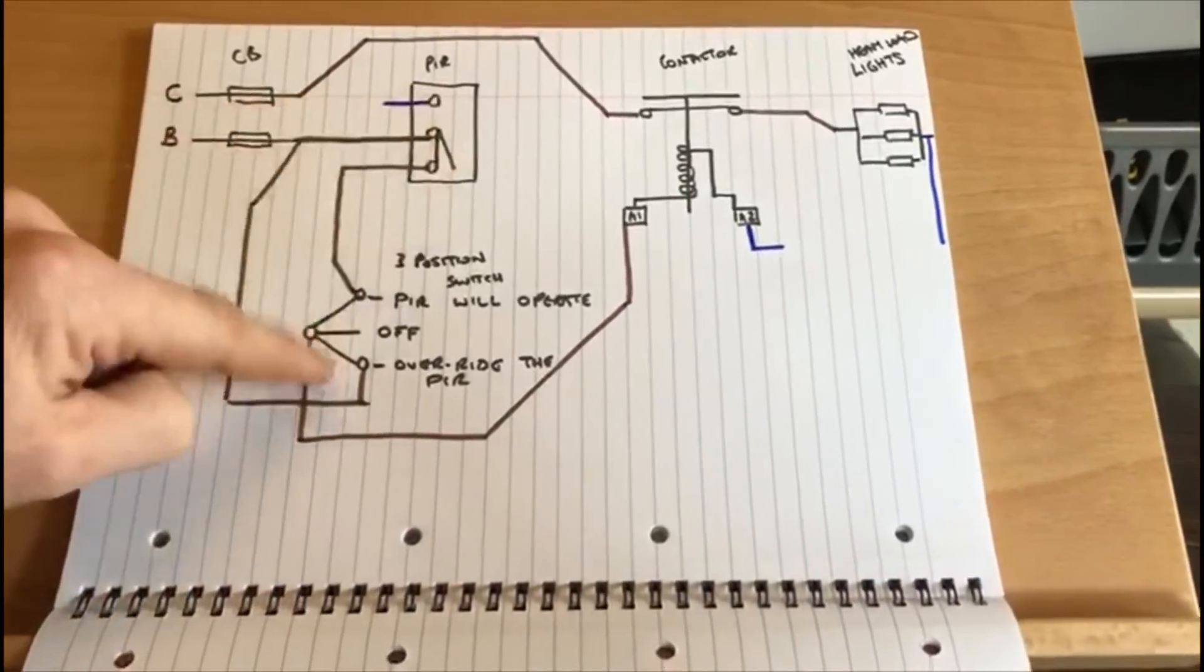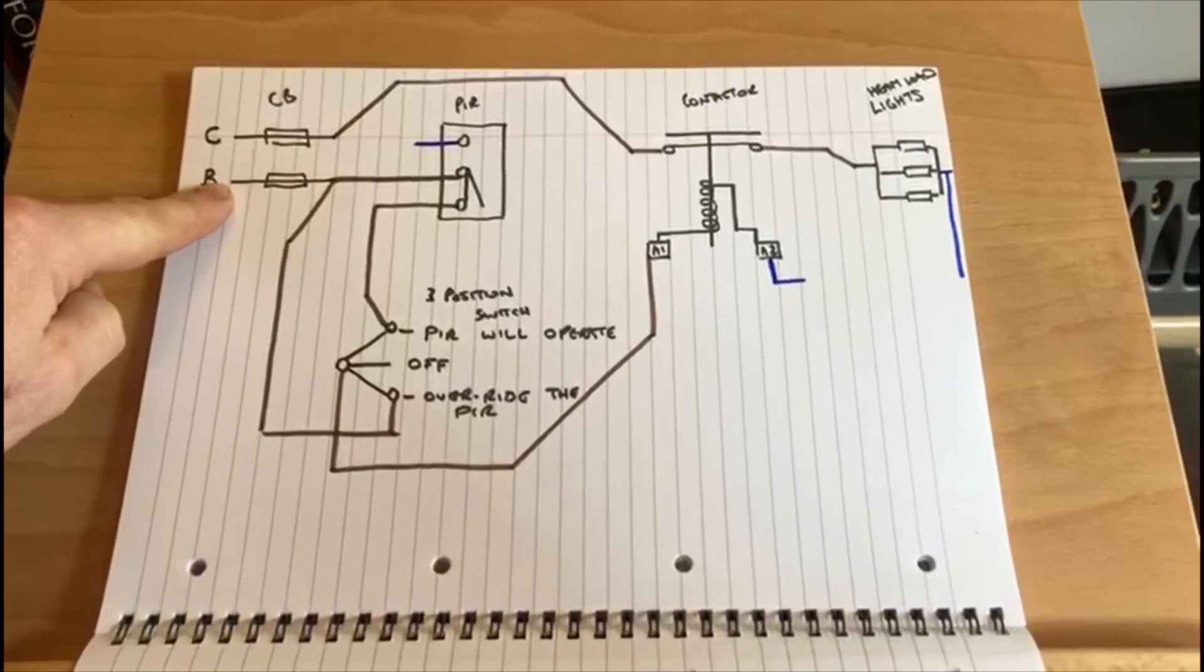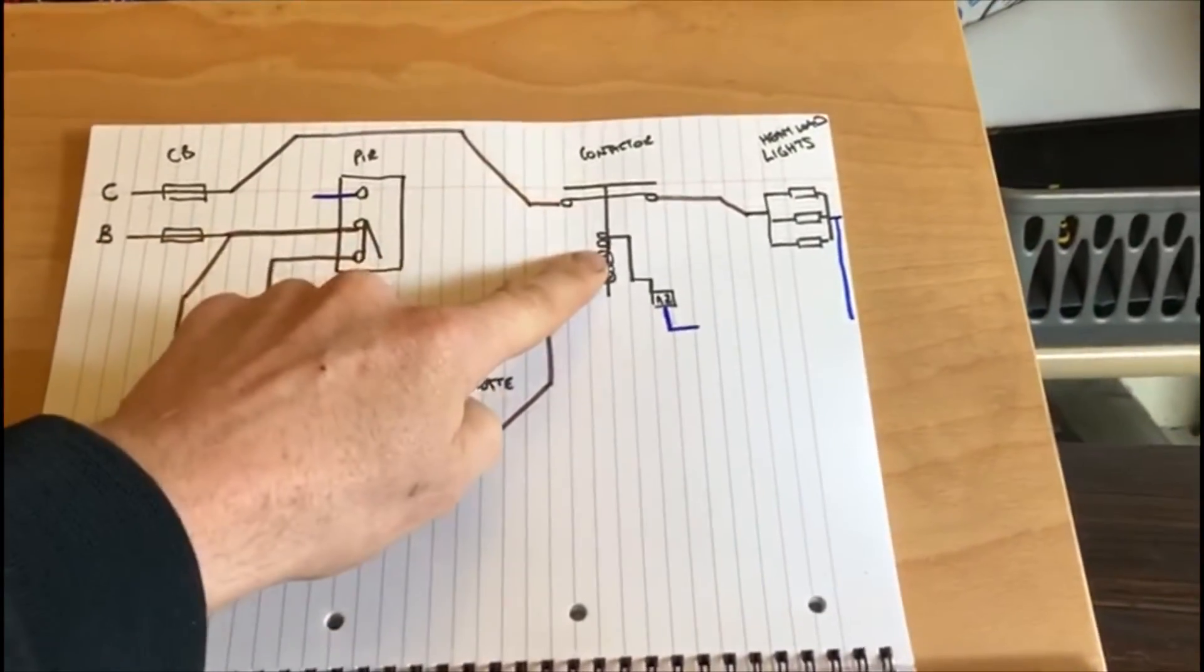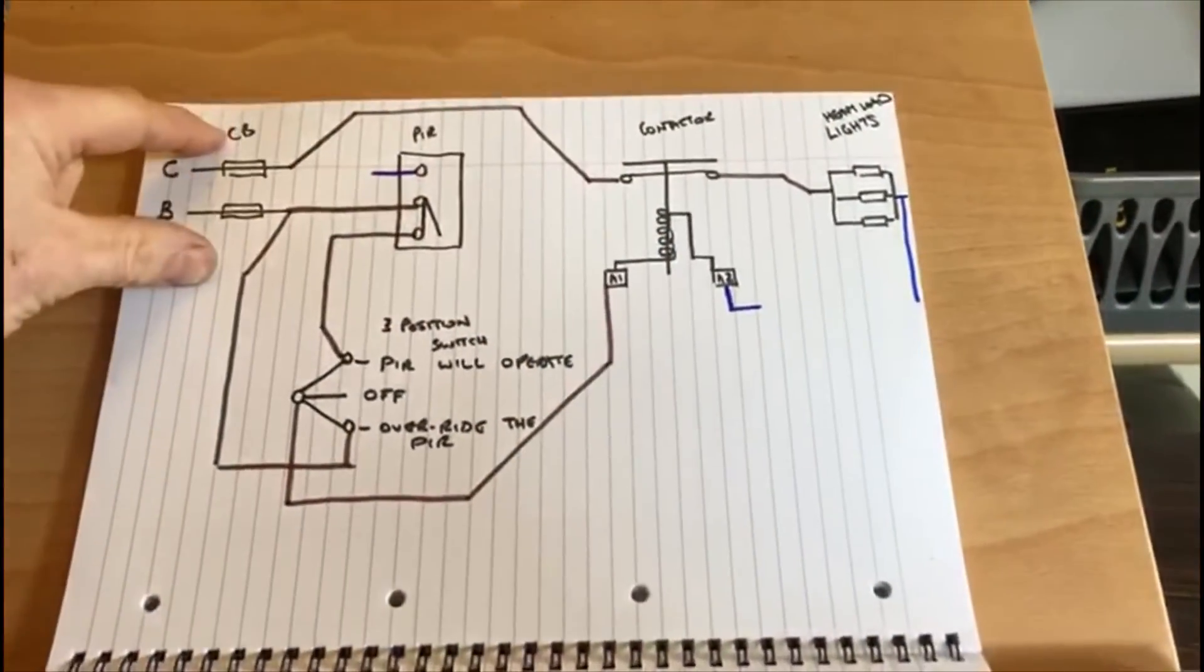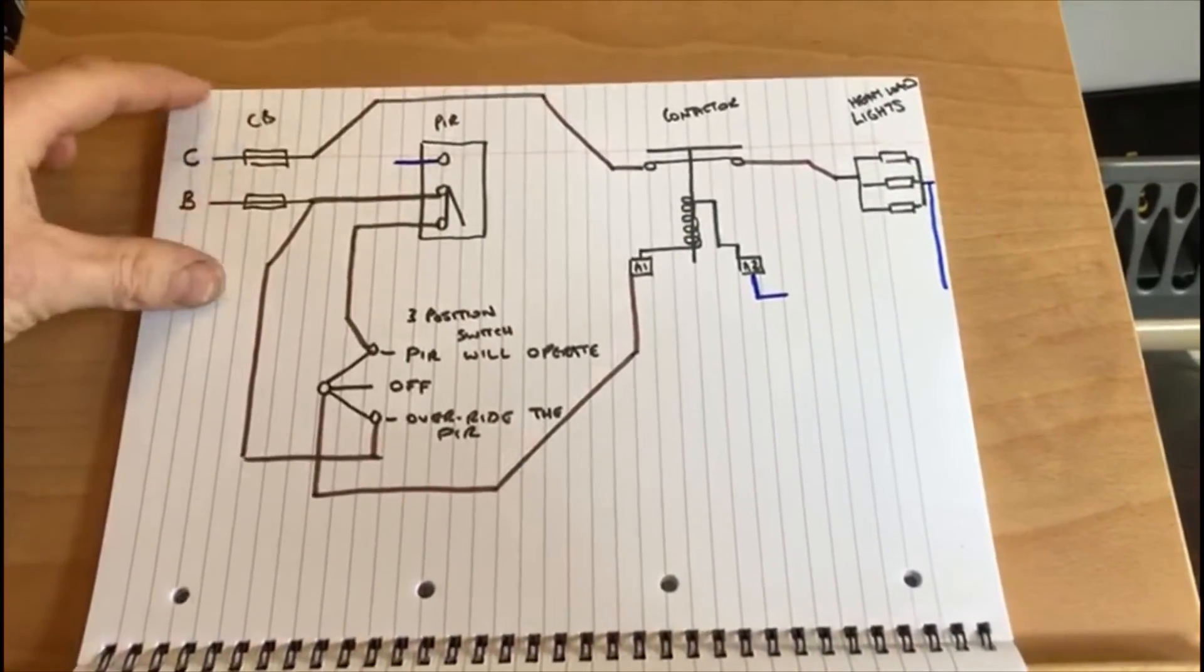These, only this circuit would need to be isolated. However to work on the contactor both circuits need to be isolated. That's really important to know that and again it needs to be labeled up so that is obvious as well.